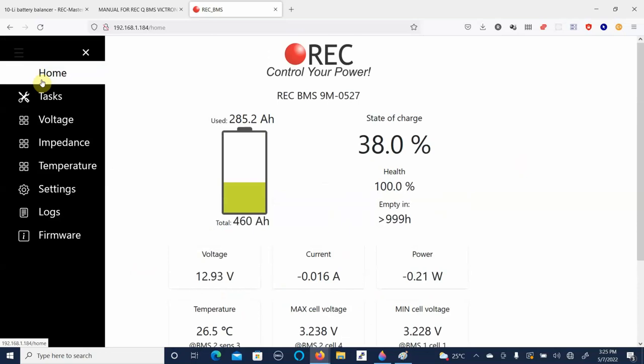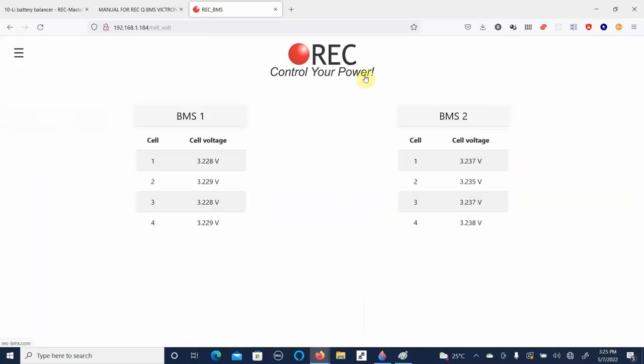Now, next thing we can do is look at our voltages. You see here that we've got BMS number 1 and BMS number 2. If you have more than one BMS connected and you only see one, or they both say BMS number 1 or something like that, you likely have your address dip switches set incorrectly. So you need to go back and change the addresses to number 1 and number 2. You can find that information in your manual.